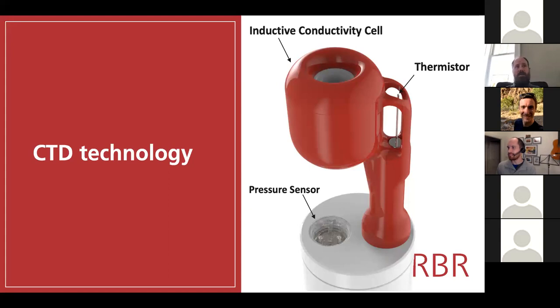But the second fundamental way of getting some current into the seawater so that you can measure how conductive the seawater is, is to do so inductively. And this is following Michael Faraday's principle of induction. And we'll talk a little bit more about that. But as you can almost see in this picture, there are no metal elements in the seawater in the conductivity cell. There is a red plastic exterior and a white ceramic interior. The only metallic elements here are the thermistor and the pressure gauge itself, neither of which are involved in the conductivity measurement. And so there is no metal touching the water that has an electric current going through it. And that's important, as we'll see later.